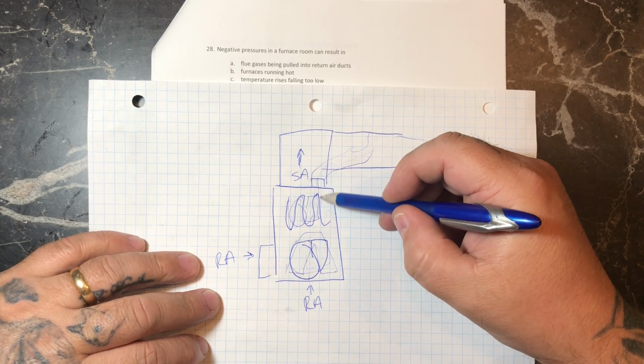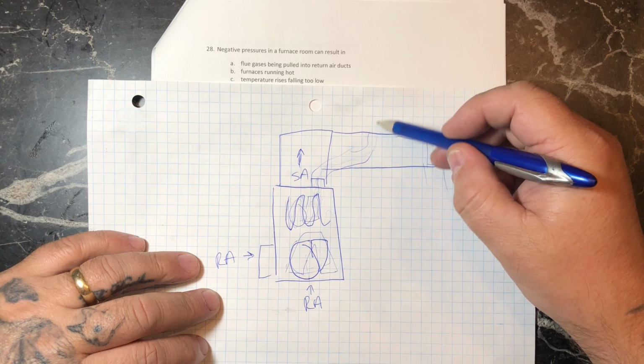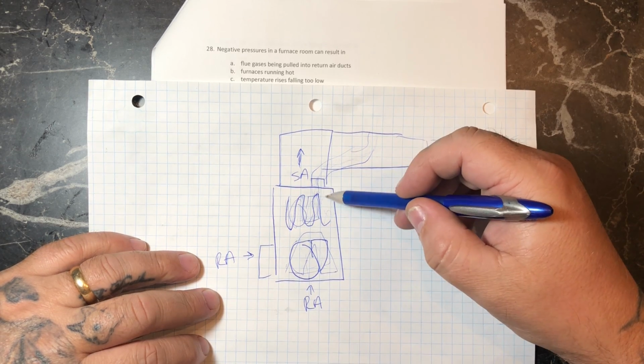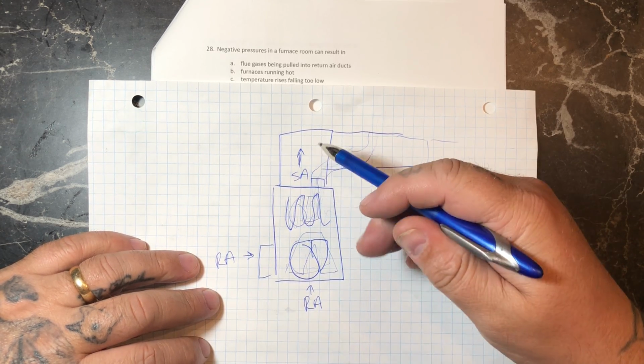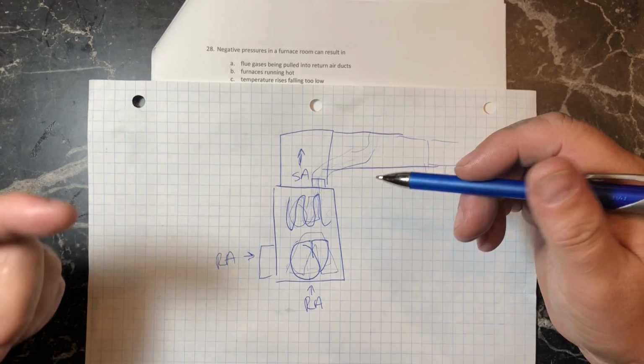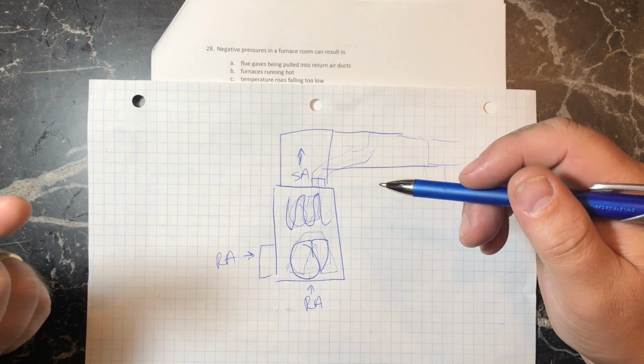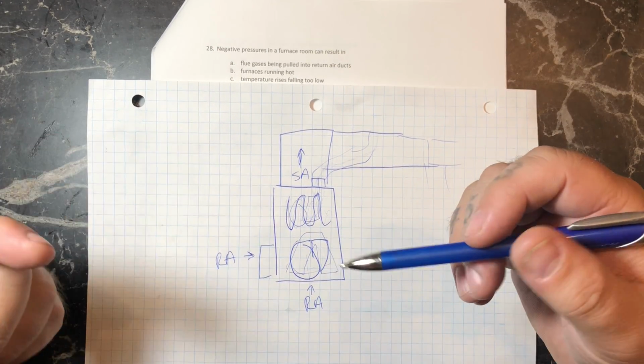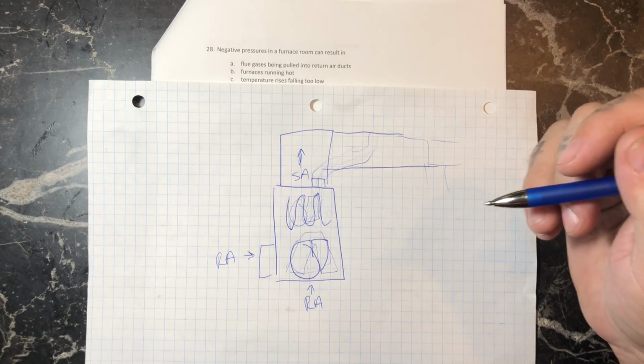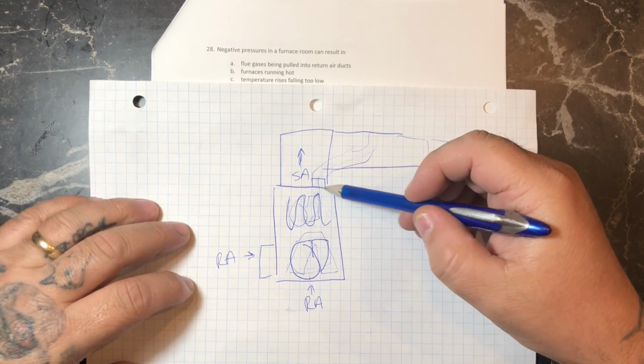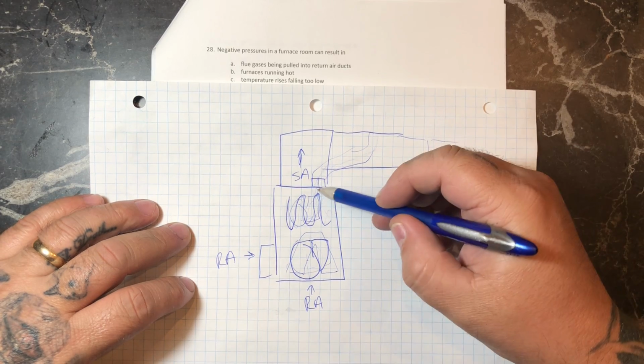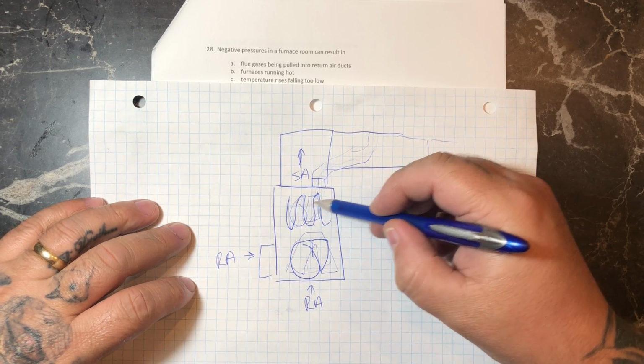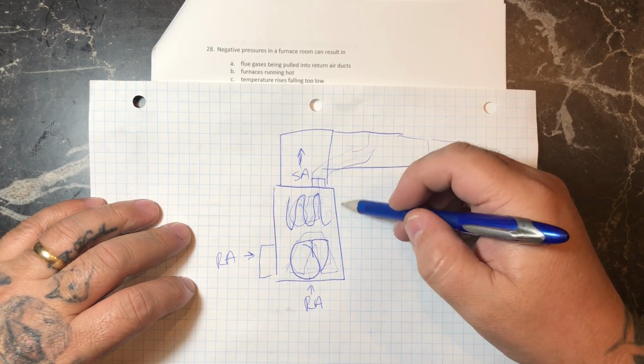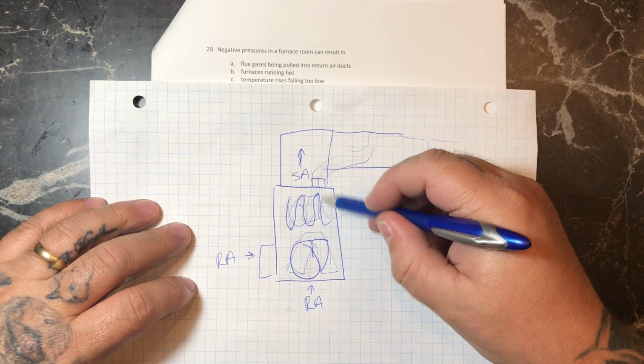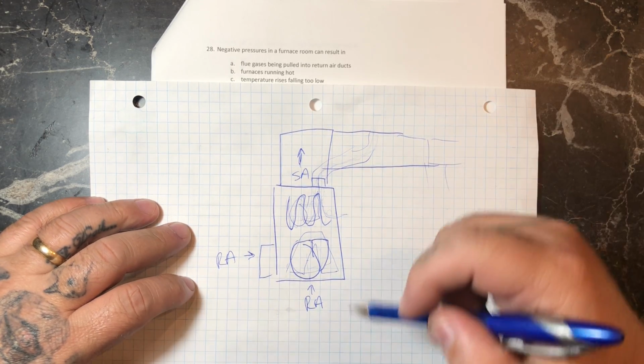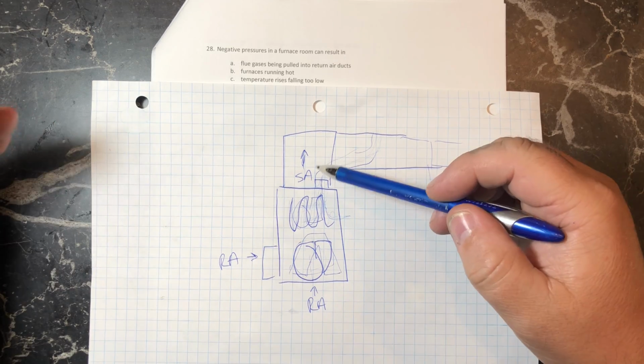If I had just a solid chimney going from this, when that hot air rises, it starts to create a negative pressure in there, and it's kind of like sucking through a straw with your finger over the end of the straw. You can only suck for so long, and all of a sudden the straw starts to collapse on itself, and air doesn't move through it. So in order for this to work properly, they'd actually have an open area here, which would allow air from the room to travel up in there and help that hot air rise up the chimney.